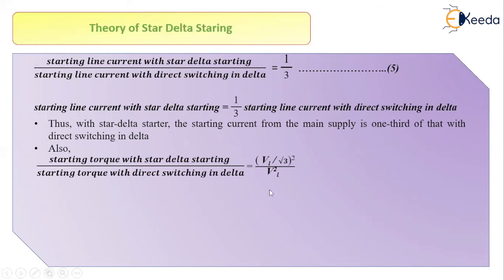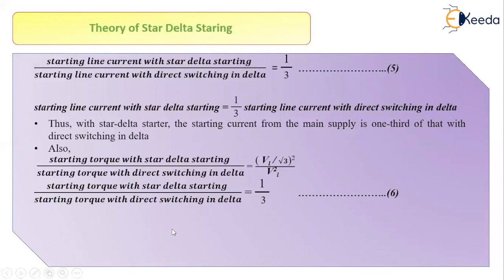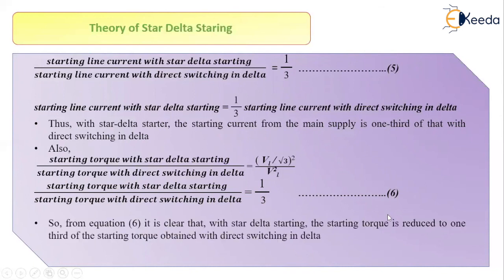A similar result applies to torque. The starting torque with star delta starting is proportional to (V_L divided by root 3) squared. Taking the ratio: starting torque with star delta starting divided by starting torque with direct switching in delta equals (V_L divided by root 3) squared divided by V_L squared. Cancelling terms, this ratio equals 1 by 3 — equation 6. So starting torque with star delta starting is 1 by 3 times the starting torque with direct switching in delta. Using star delta starting reduces the starting torque to one third of its value compared to direct delta connection.